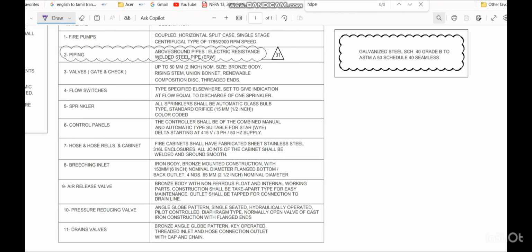And now we are going to see some important materials which are given for the project. First, the fire pump we already discussed, it is a horizontal split case. Coming to the piping for the project, for the above ground pipes, they have mentioned ERW pipe has to be followed, and the material they have given is galvanized steel schedule 40 grade B ASTM A53 seamless pipe. So we have to follow carbon steel pipeline, ASTM A53 is the standard we have to follow.